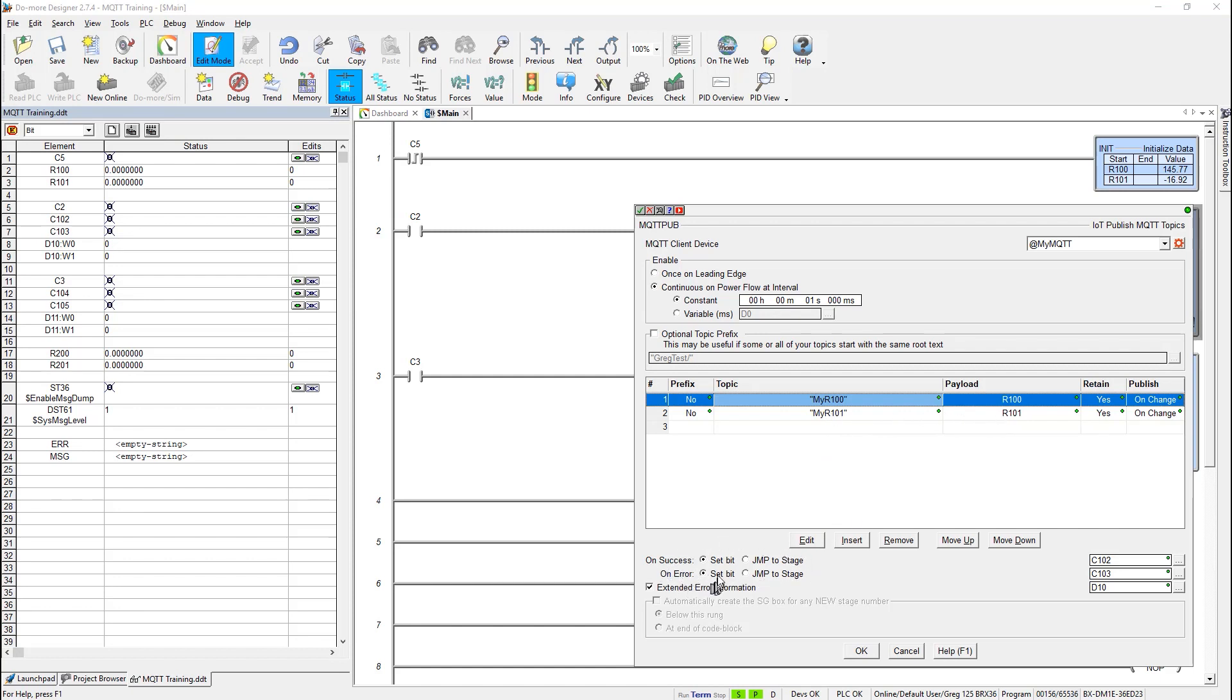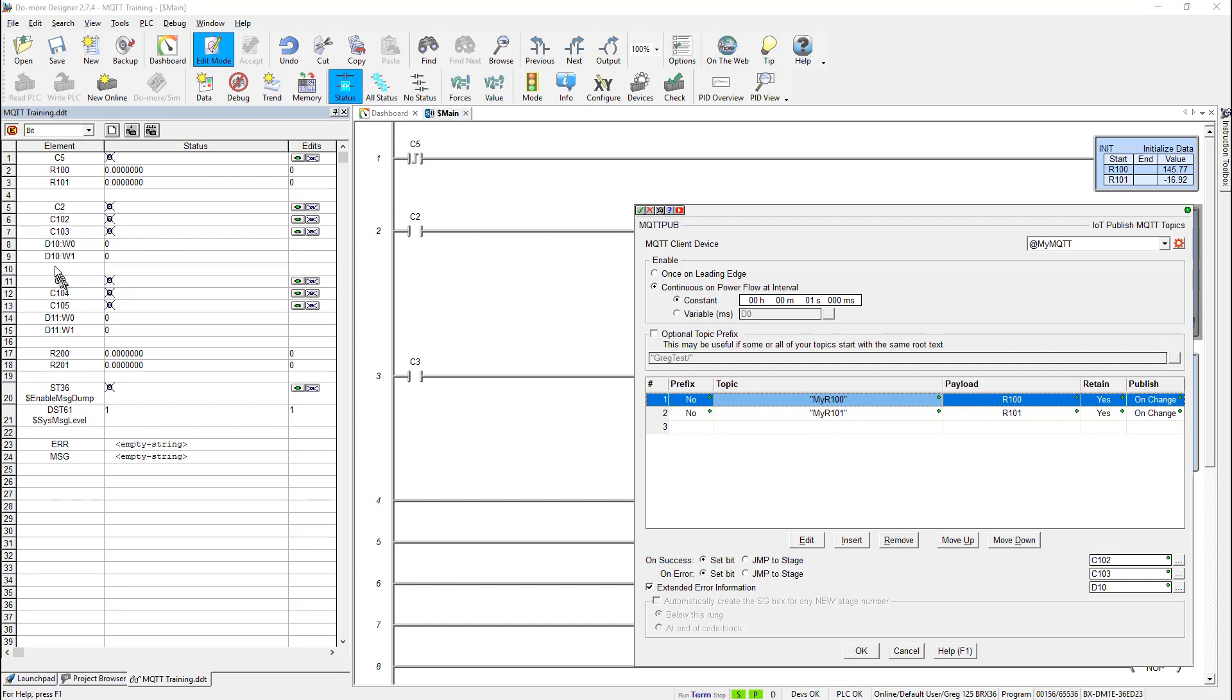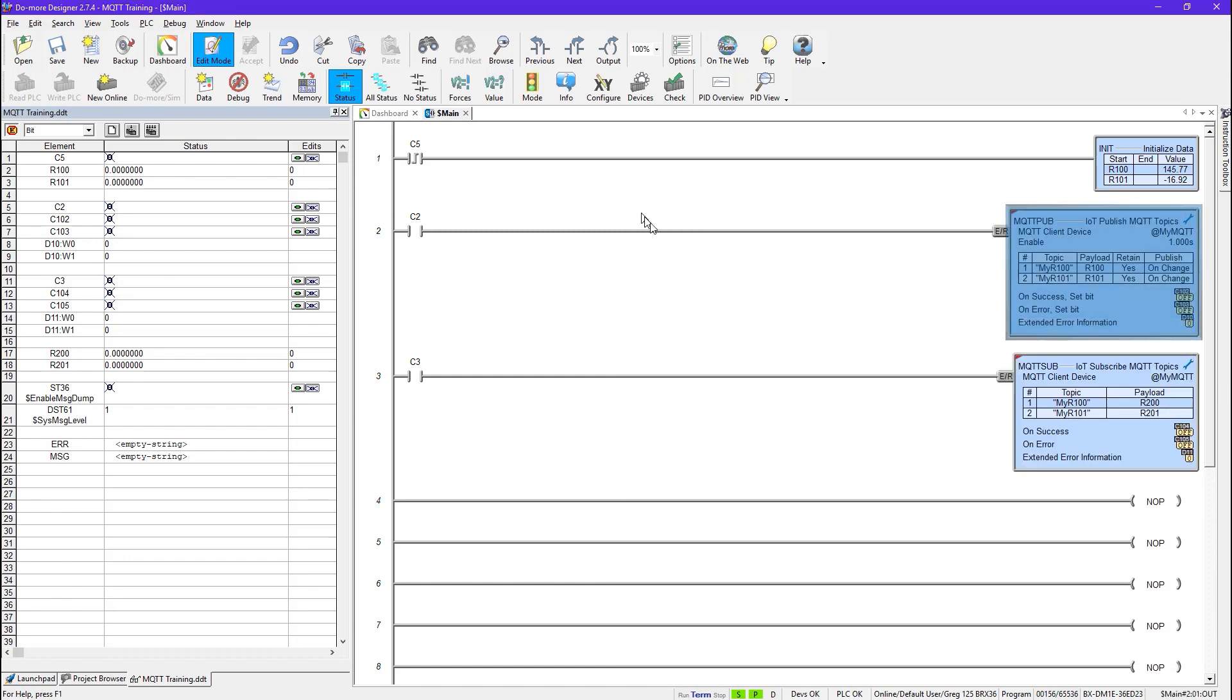Now also of course you have the on success and on error behavior. In this case I'm choosing to just set some bits. Probably normally I would use stages to do this. And then there's also the extended error information that can be stored in a double word, D10. Now the thing about this is that the lower part of this word will contain an error code if it fails. And the upper word will contain a topic number of the first topic that failed. Say you had a list here of ten things and maybe five of them failed. It would only point to the first one. So as you can see over here in my data view that I have put up here. I divided D10, which is my extended information double word, into the lower word and the upper word so that we can see that. So what I'm going to do later is I'm going to generate an error so you can just see that happen. So that is the MQTT pub instruction. That's pretty straightforward and simple.